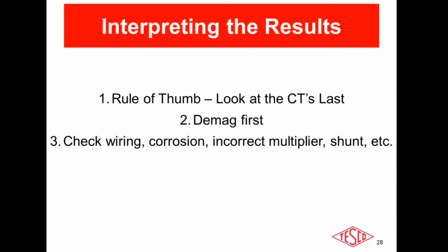And we also had a question on the chat from Kristen. Can Demag be done at a customer site that has load? Yes. Doing the Demag does not affect the customer load at all. So yeah, no worries there. I've done it many a times.